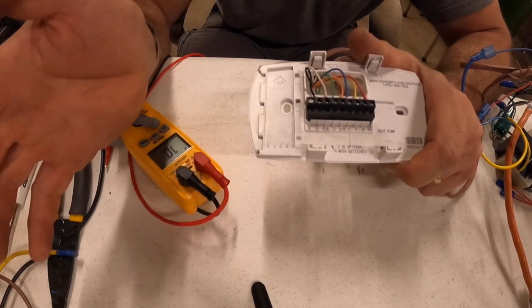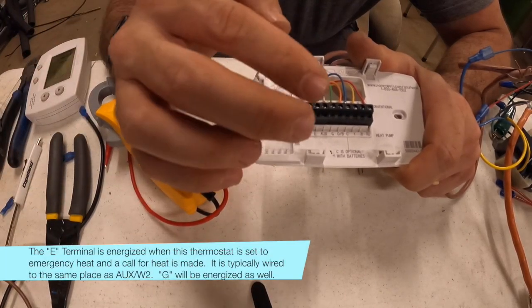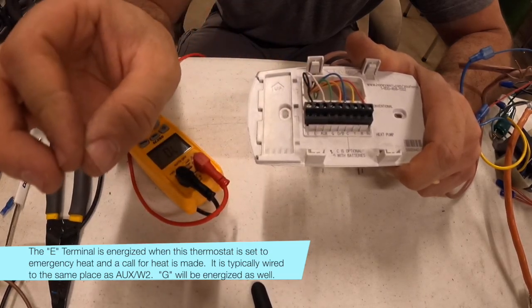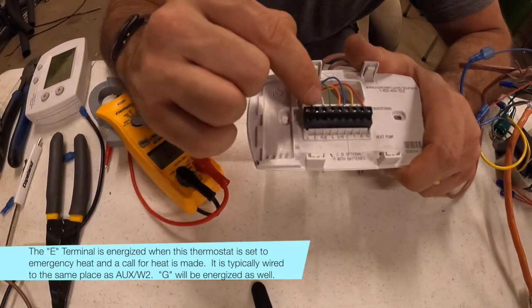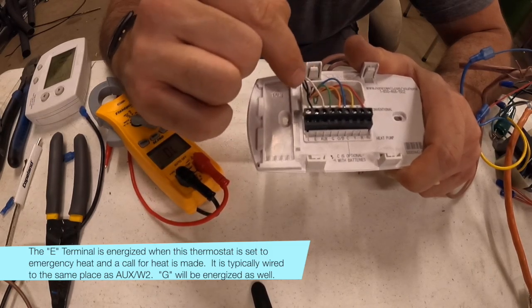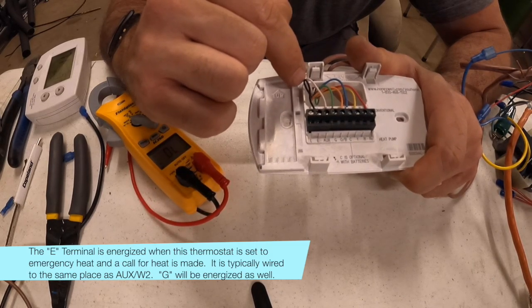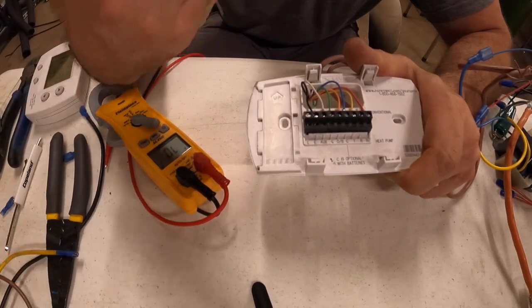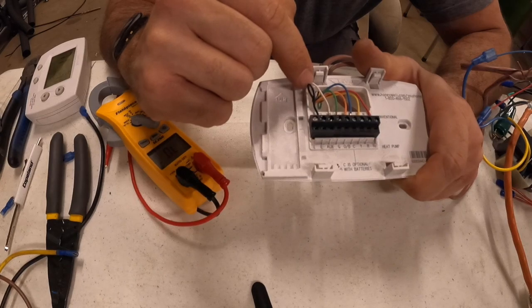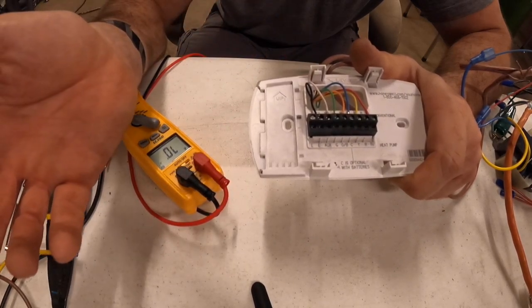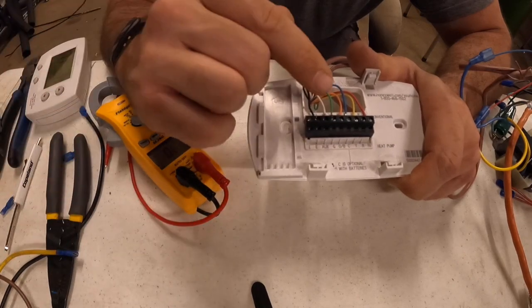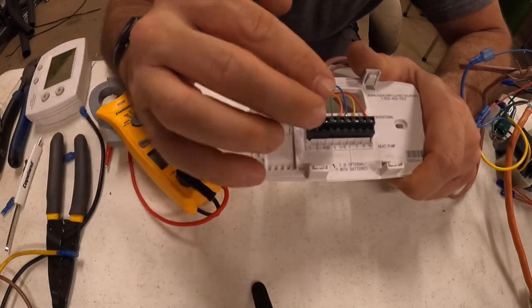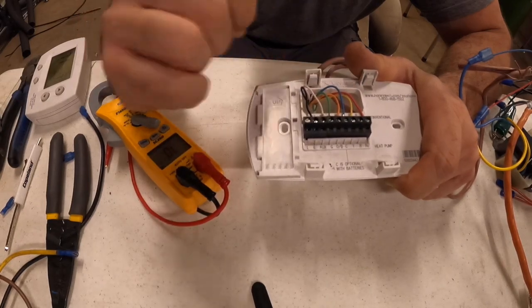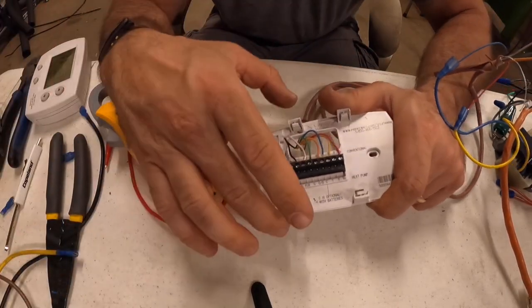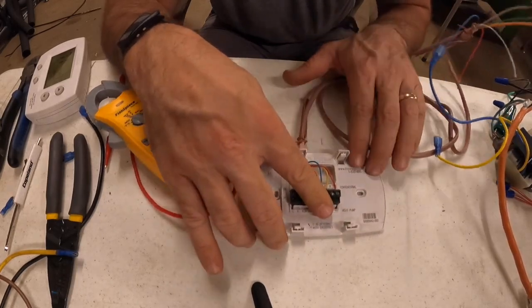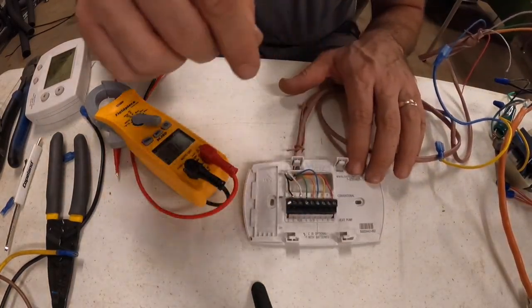Some thermostats don't have that option. This one does. You can call for emergency heat, and it will only call for the fan. It'll energize G, and it'll energize this wire. Basically when you get into the unit, these two wires are the same thing, so it's calling for auxiliary heat. Emergency heat is just auxiliary heat by itself. It's not running anything other than the fan and the heat strips. When you see auxiliary heat come up, your first stage of heat, which is your heat pump, has already been energized. Now I'll go in and show you how this thing actually works, how we're getting voltage in here.